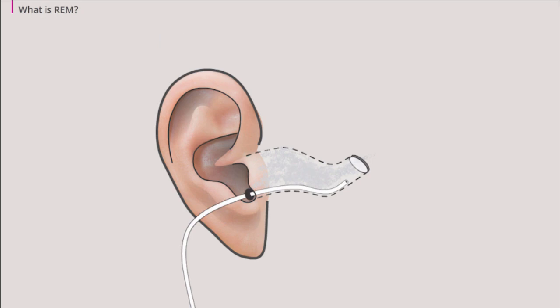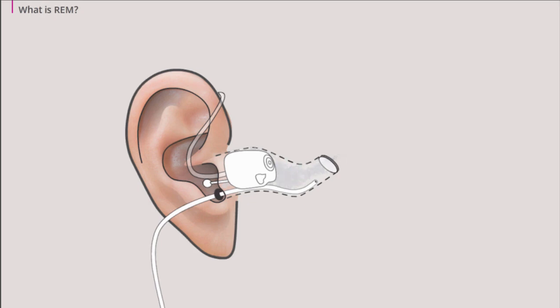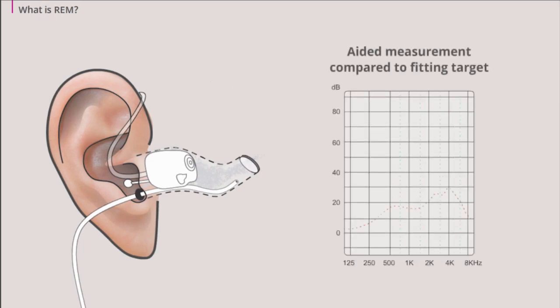Afterwards, you insert the hearing aid into the ear canal with the probe tube still in place and the real ear measurement is performed again. This is because the hearing aid changes the natural resonance of the ear canal. The aided measurement is then compared to the fitting target. If the target is not matched, fine-tuning can be made accordingly.